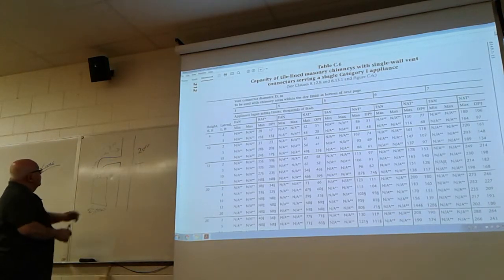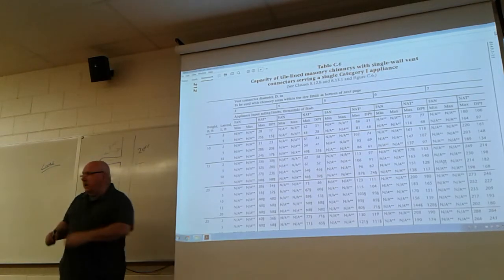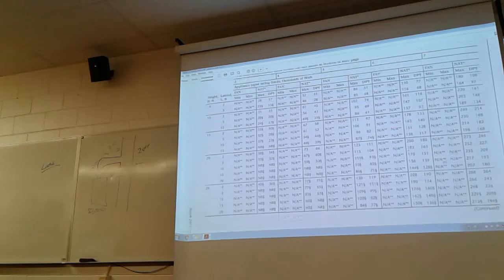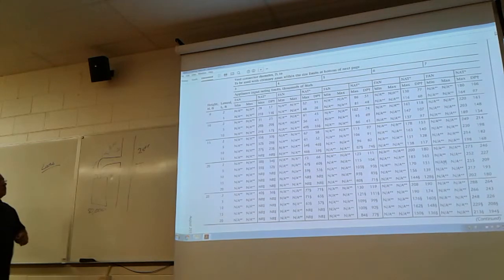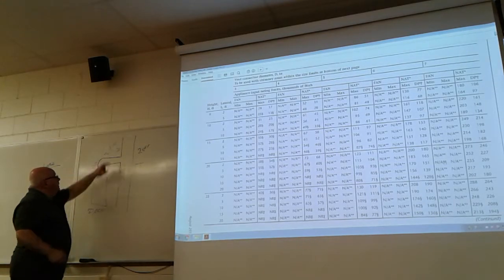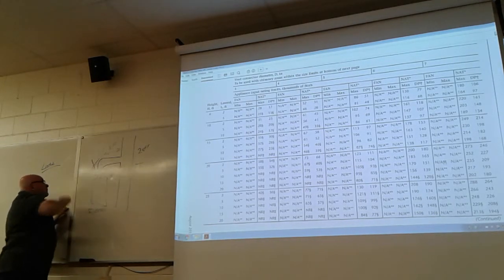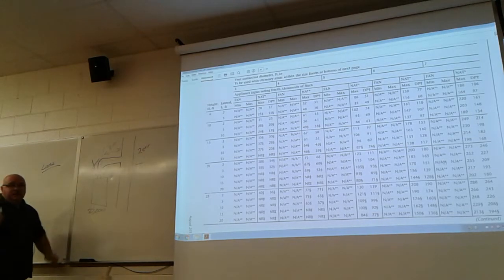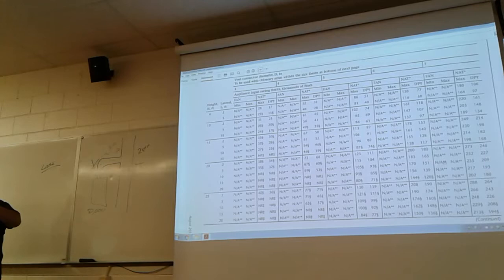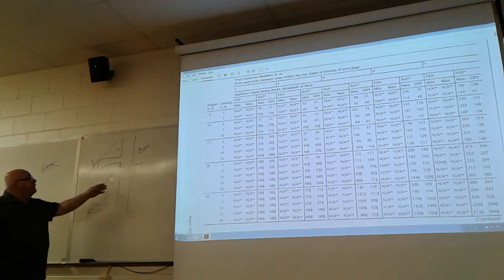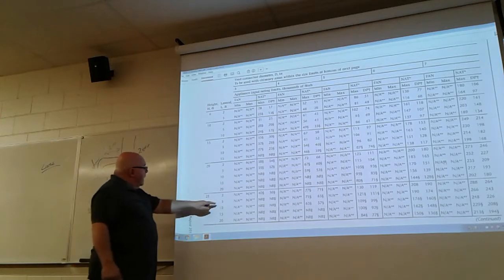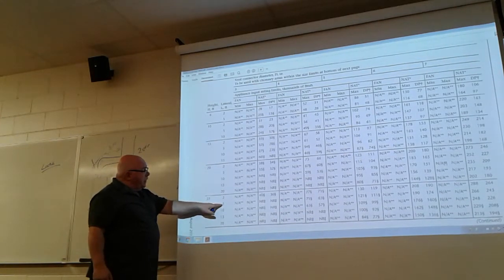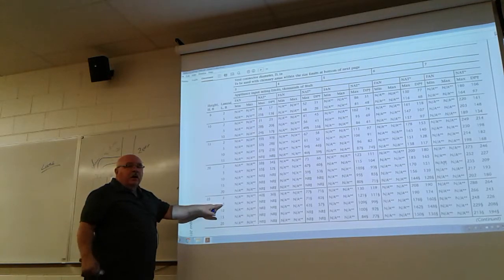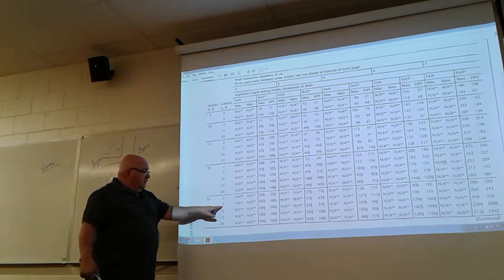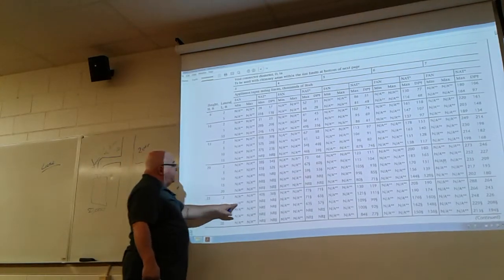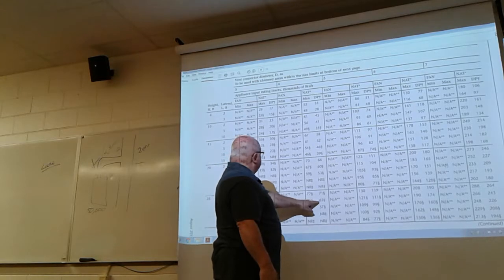Okay. So I got a height of 25 feet, so it's down here, so I just move that up. And I have a lateral of 3 feet. This 2-foot rise right here is just useless information because single appliances use lateral, multiple appliances use the rise. So I've got 25 feet, 3 feet lateral. So with the 3 feet lateral, do I go to 2 or do I go to 5? What's the worst case scenario? What will slow the gases down more? Longer. Go down to the 5.